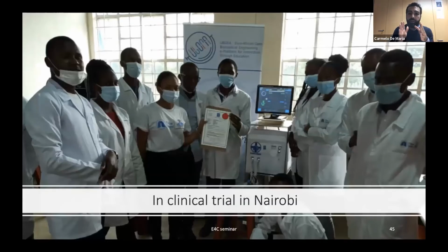And for example, the ventilator developed by students in Nairobi, following the design specification indicated in UBORA, allowed those students and the entire university to go to clinical trial. I mean, a student's project in clinical trial to save lives is amazing. I mean, in 3 months. This is an impact. Even if they saved one life, or if they gave 10 more days to a person, this is an impact. But they achieved that impact because the design was made in order to be ready to be certified. Okay, this is the most important part.